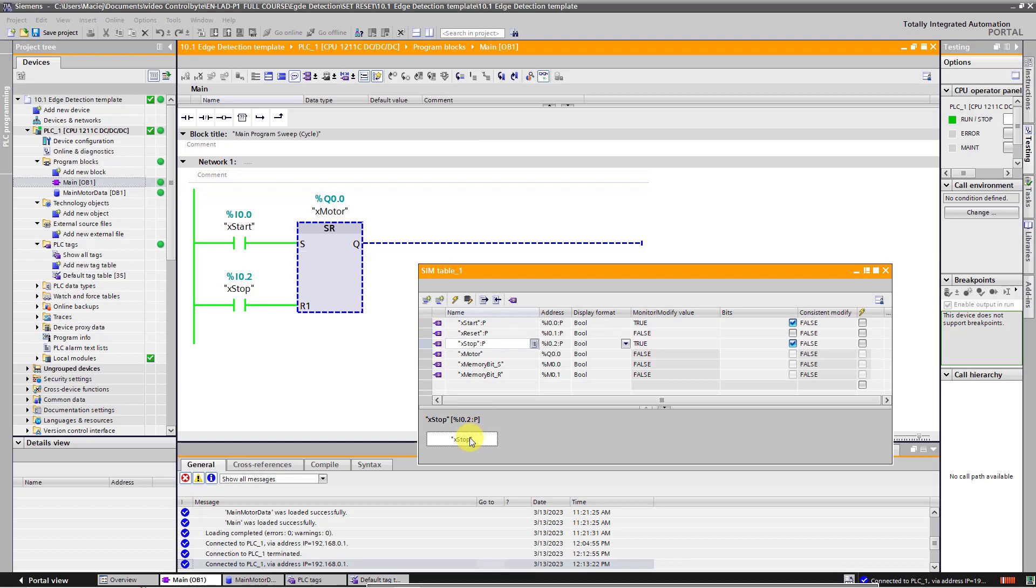OK, so when I press on the stop button, the motor will stop in this moment. The stop button is still pressed on. But when start button is damaged, after releasing the stop button, the motor will start automatically. It could be dangerous situation and you can expect that in your application.